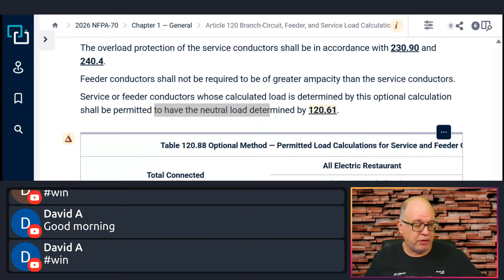So even though you're going around as an electrician, in the real world, you're going to be gathering all of the nameplates. Again, you're going to be wiring all these things if it's an all-electric restaurant. So if this is only for new, by the way, you should have a list, or somebody should be able to provide you a list of all of the equipment that's going in there, especially if it's all electric. I mean, you're installing it, right? So you have this list. So you can do a separate calculation, okay, just to find what the minimum size of the neutral could be.